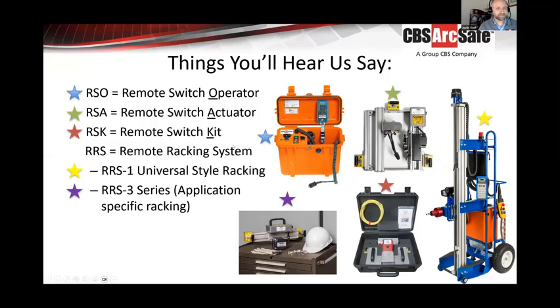An RRS is remote racking system. The big blue cart here, that's our universal system. That motor can go up and down for switchgear that's high up or low to the ground. That's for anything that uses a rotary style racking mechanism. And we have application specific solutions, which are designed just for one type of breaker.